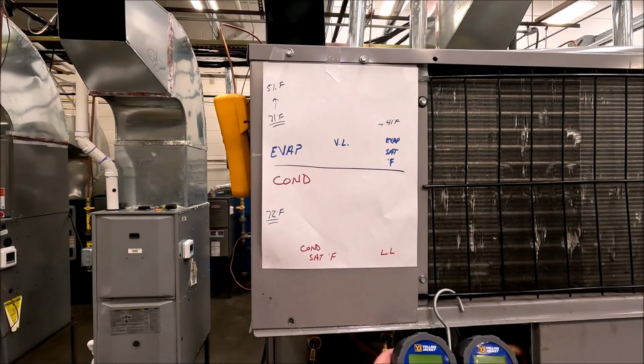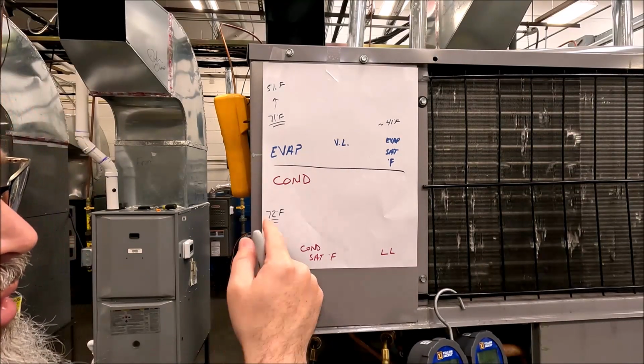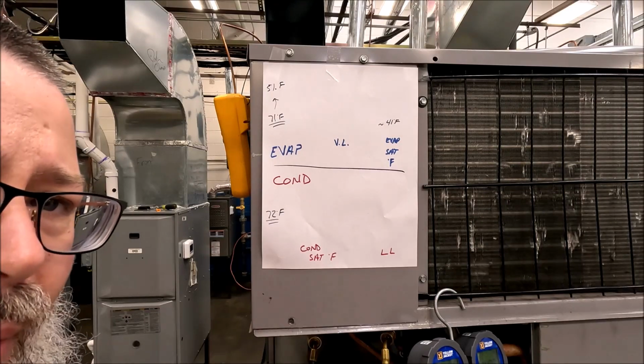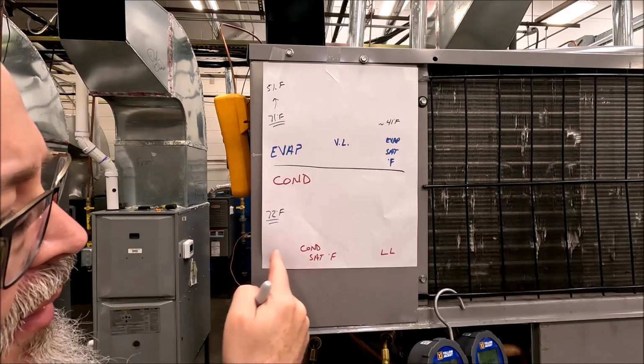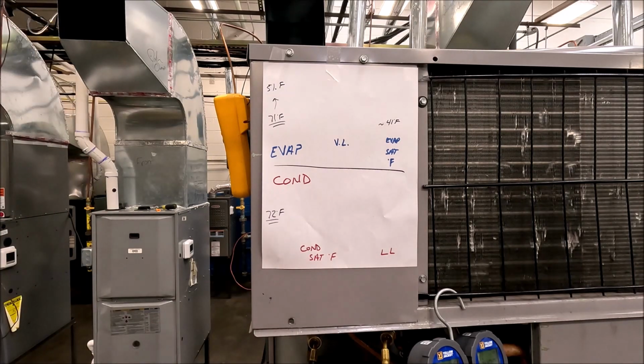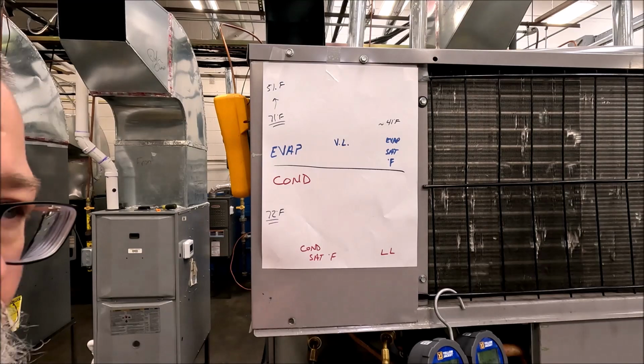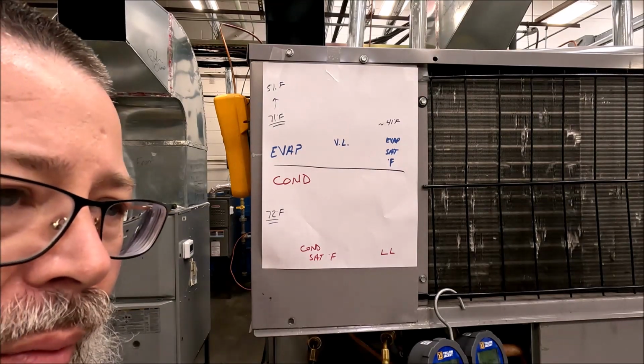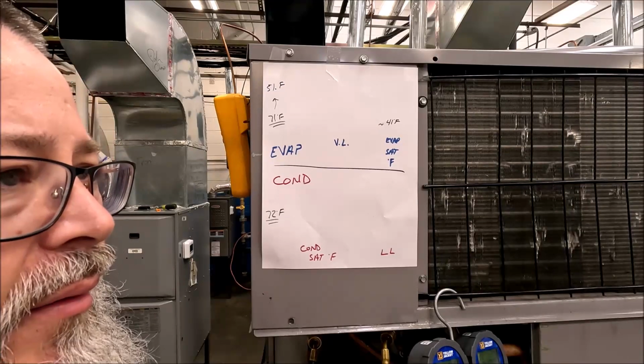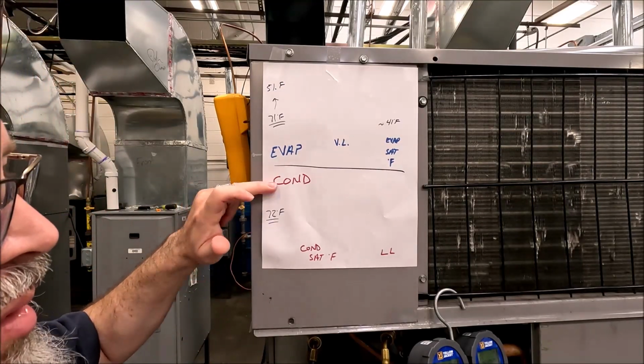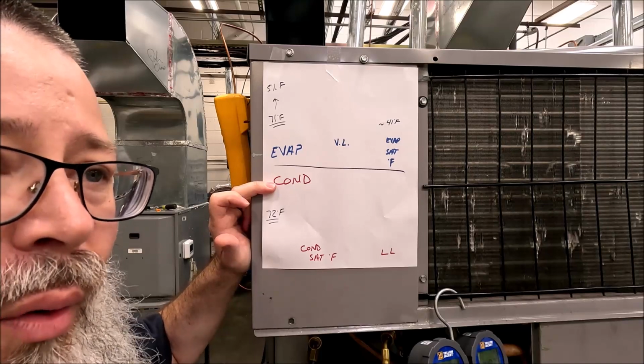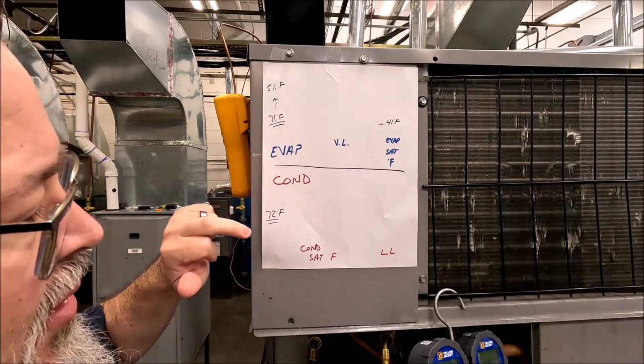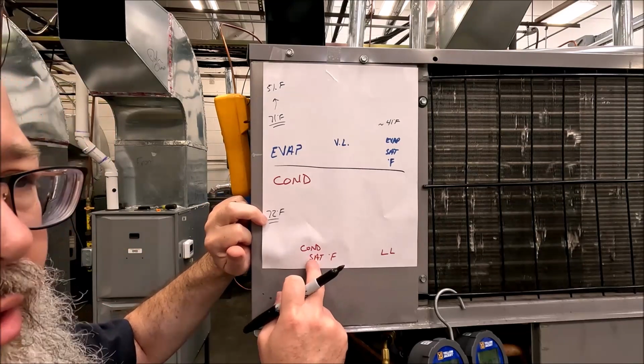So what I'm gonna do is turn it on real quick and get both these gauges back on. And we'll finish up with the condenser before we look at the gauges and talk superheat and subcool. So 72 going in this condenser. Step right here, look at the model number. If I'm not mistaken, this is like a 14 SEER model. Just offhand, you could research your own model number. But condensers always have to be warmer than the air that's going over them. Evaporators always have to be colder, so I have to be warmer than 72 degrees for my saturation point.